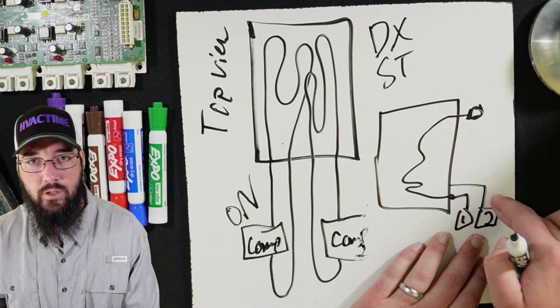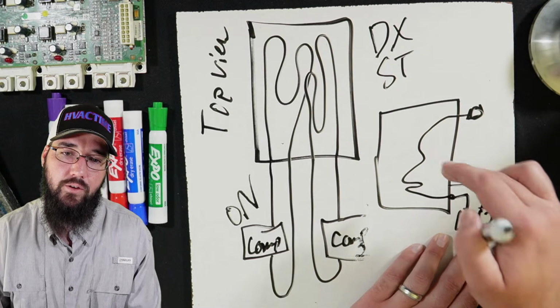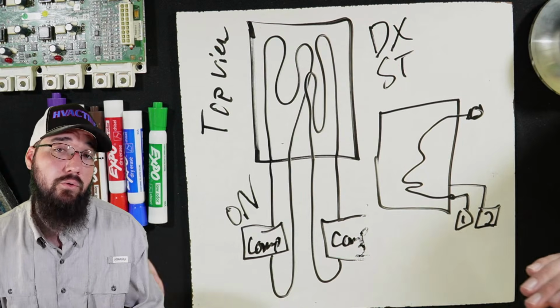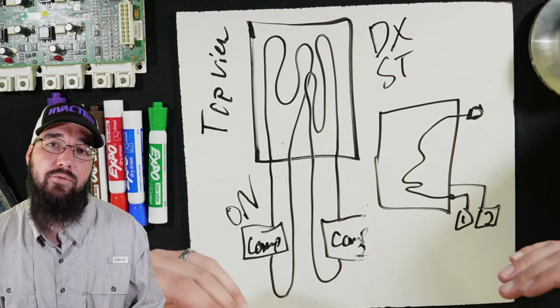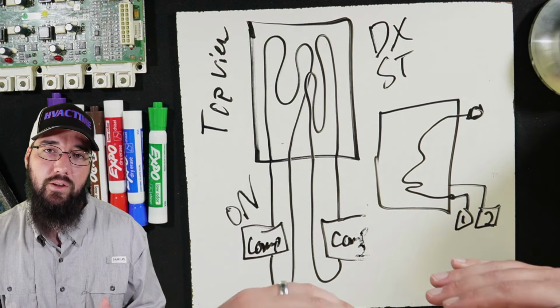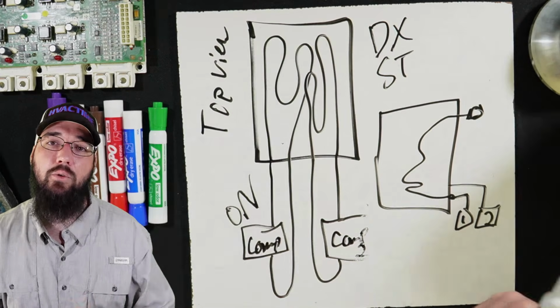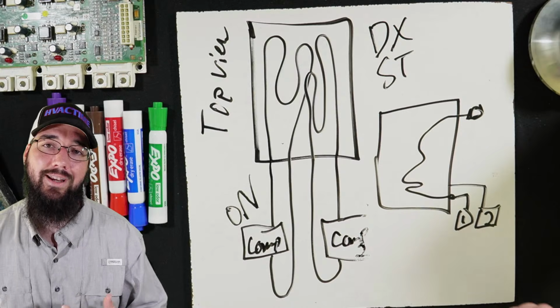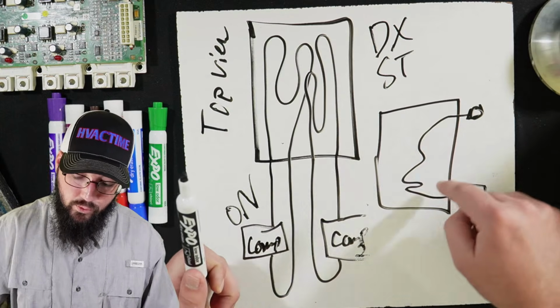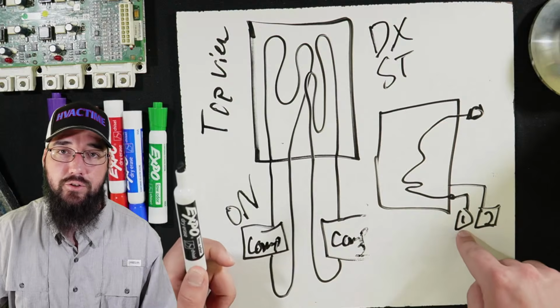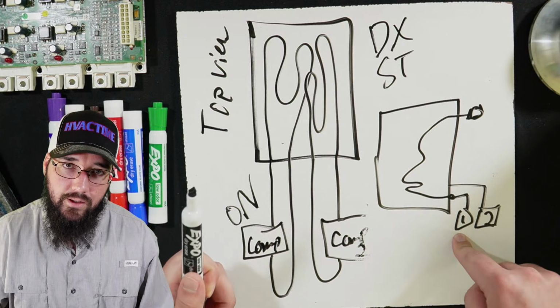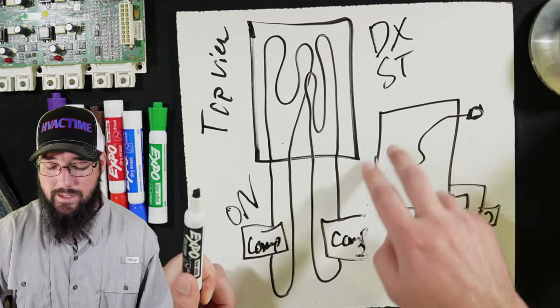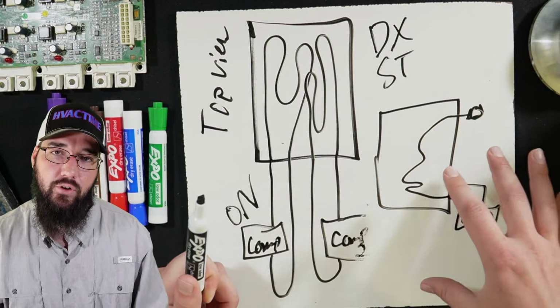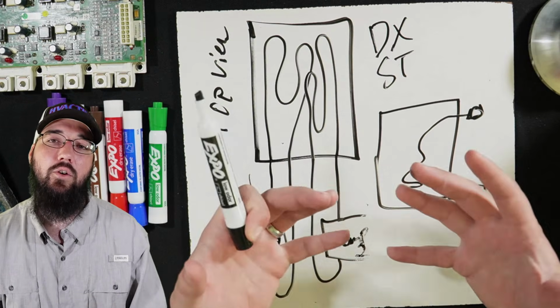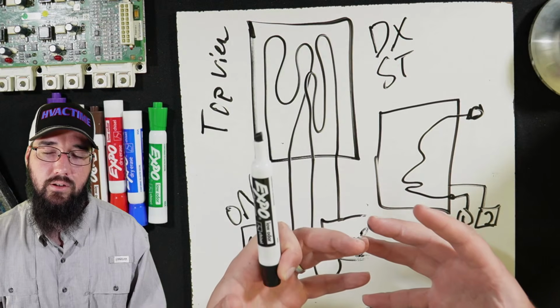But then circuit 2 comes in and kicks in to help circuit 1 on this coil, and all of a sudden both are running at, say, the low 40s in saturation, and now we're achieving that supply air set point we're trying to get to. And again, this saturation dropped because now it's sharing that heat load with another circuit, and it's not got the entire heat load to itself.